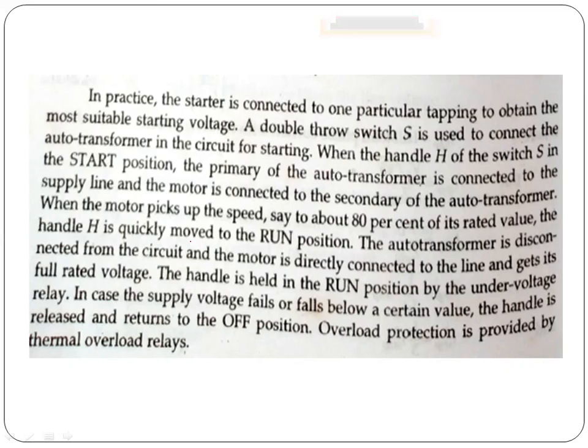The handle is held in the run position by the under voltage relay. In case the supply voltage falls below a certain value, the handle is released and returns to the off position. Overload protection is provided by thermal overload relays. These are the basic things.